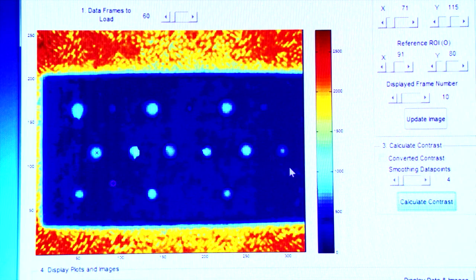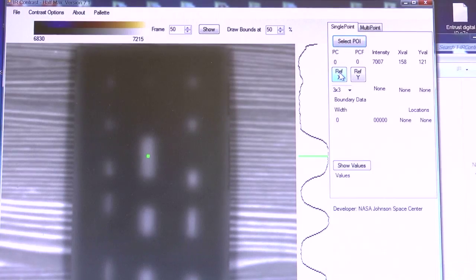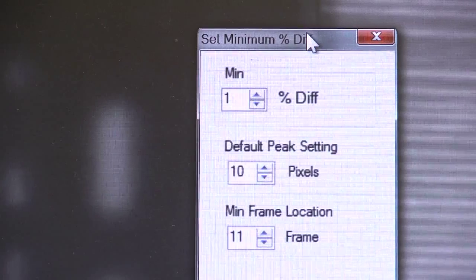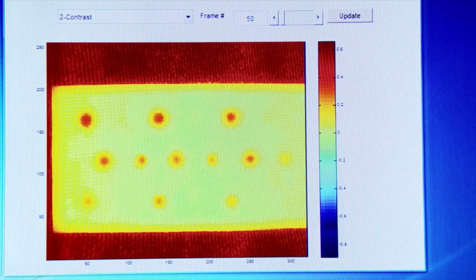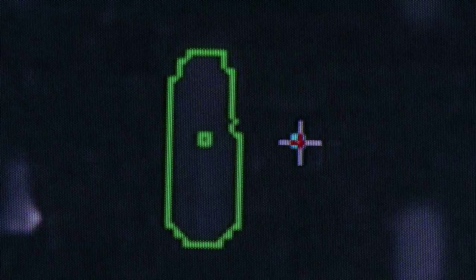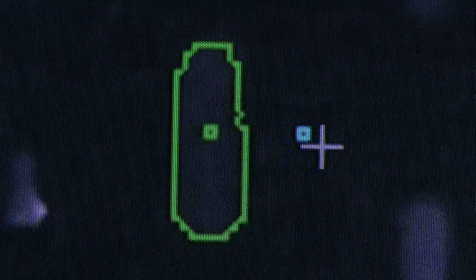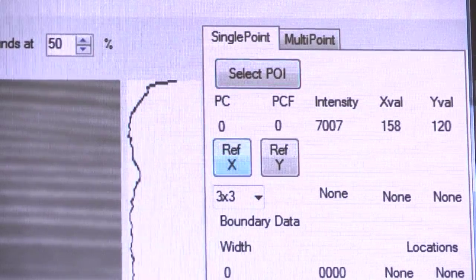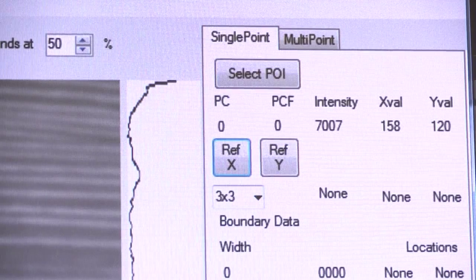The software that NASA has developed is a method called Infrared Contrast. It's a post-processing software. Essentially, it analyzes the data by converting it into contrast data, and you can measure that indication in terms of normalized contrast and parameters based on normalized contrast.